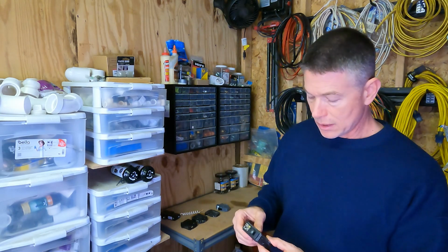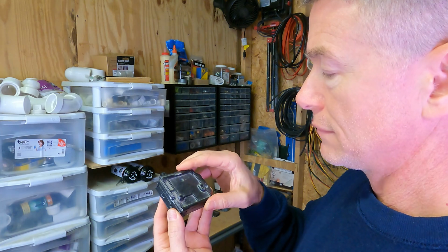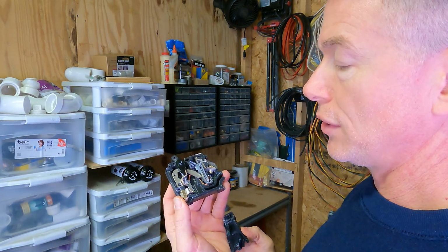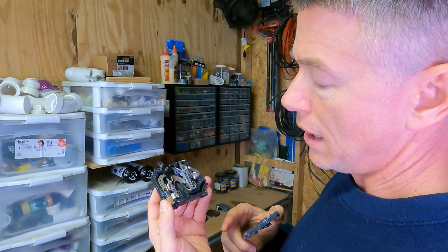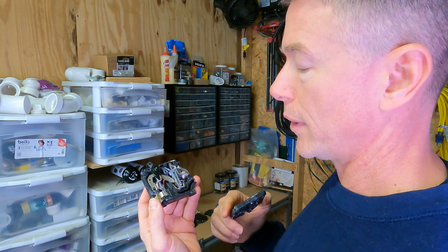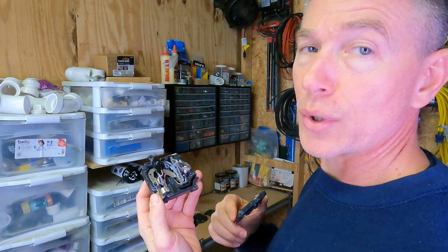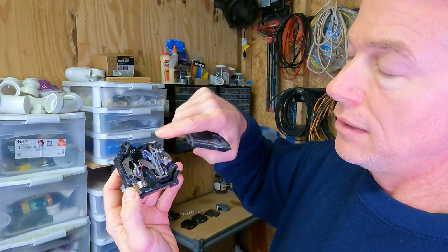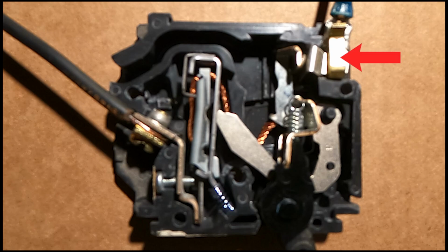In this video, I took this Square D breaker, similar to the other one, and I basically drilled out the rivets so I could show you the inner workings of the breaker. Now, I'm going to attempt to short circuit this breaker and film it in slow motion so you're able to see what exactly happens during a short circuit. I'm also going to attempt to overload it so you can see how the bimetallic strip right here works to break the circuit in an overload situation. So stay tuned. This is where the breaker connects to the line side of the system, and just to the left of it is where it'll disconnect the circuit. This is the latch point, and this is the magnetic armature that will move away from the latch point, allowing it to disconnect the circuit.